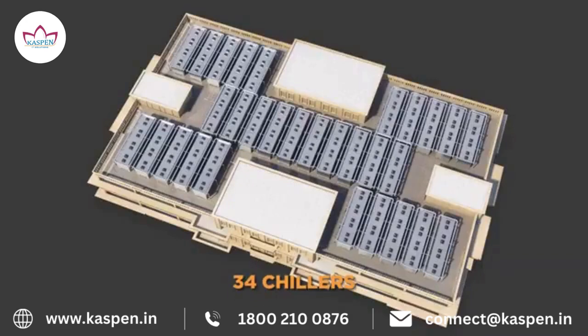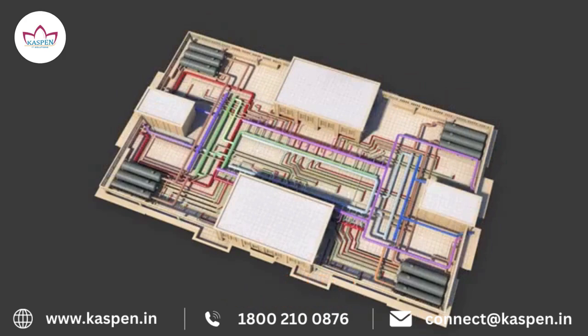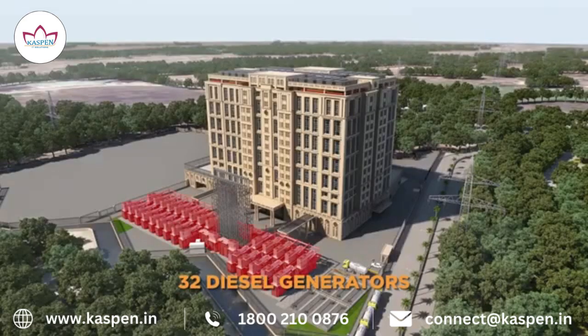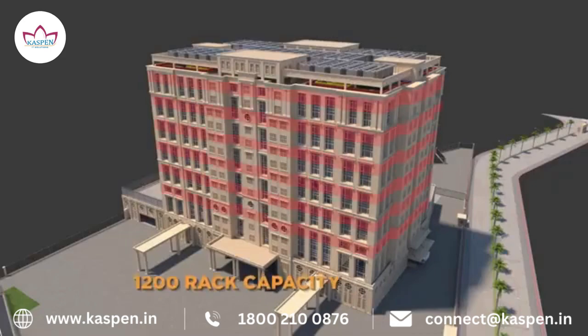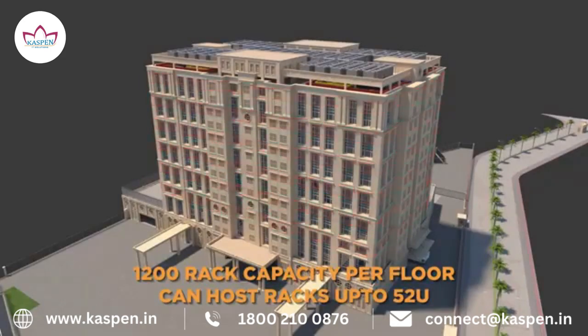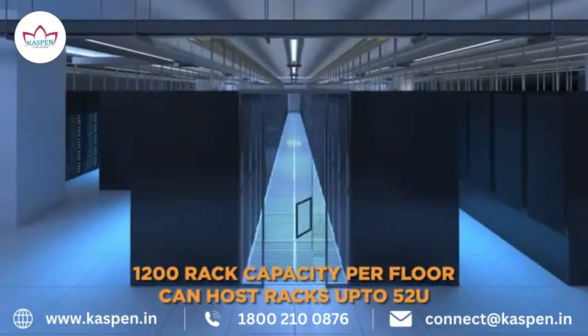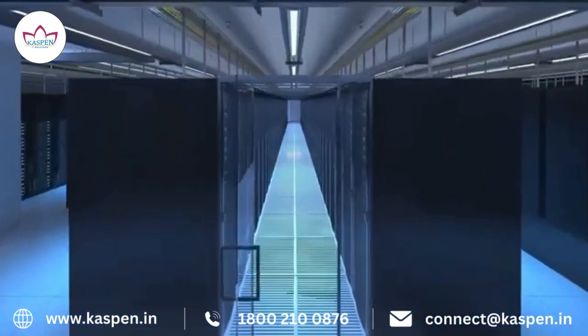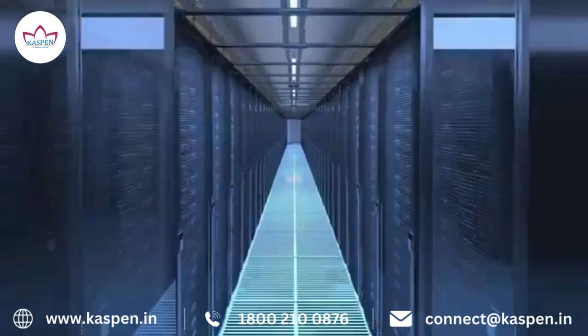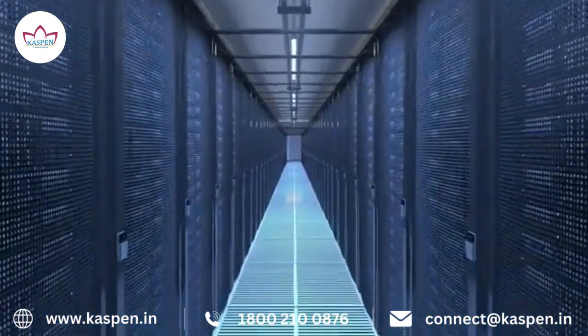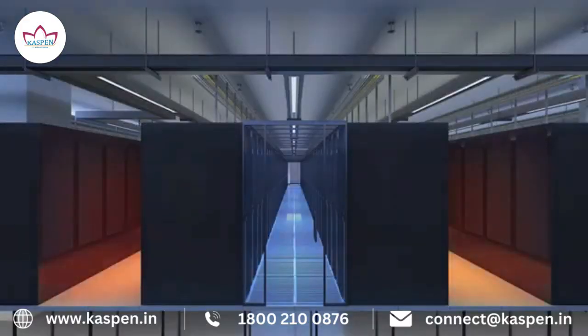The terrace of the building has chillers installed on an elevated platform and chilled water distribution plant below the platform. The backup diesel generators are placed outside the building on an elevated platform with underground fuel tanks adjacent to the same. The 6 dedicated server hall floors have a load-bearing capacity of 1,500 kilograms per square meter and can house server racks of various sizes up to 52U. Racks are arranged in a hot aisle, cold aisle configuration with cold aisle containment.